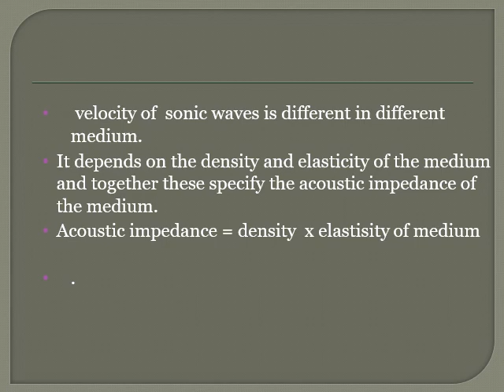So when an ultrasound beam is transmitted from one medium to another medium, because of the velocity difference, some ultrasonic energy will be reflected back due to the difference in the acoustic impedance of the two media. The amount of energy reflected back is directly proportional to the difference in the acoustic impedance between the two media and also depends on the angle of incidence of the wave at the interface. Let us understand with an example.